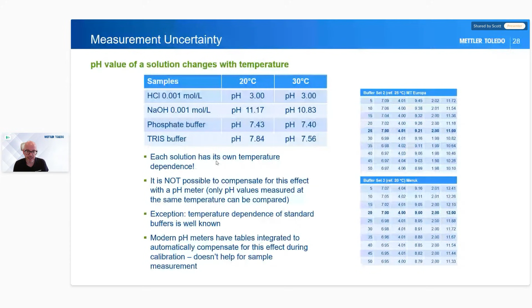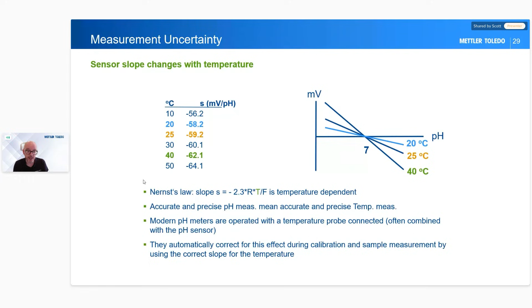Another one is that slope changes with temperature. I originally showed you the Nernst equation, where temperature is involved. So this is going to absolutely change the slope at which we take measurements. And yet again, modern pH meters normally take this into account, but it's worth checking that your pH meter does. In the Mettler meters they do, but in other meters they may not. So those are the things you need to think about, taking this temperature into account. And that again is why it's really important that we record the temperature when we take a pH measurement.